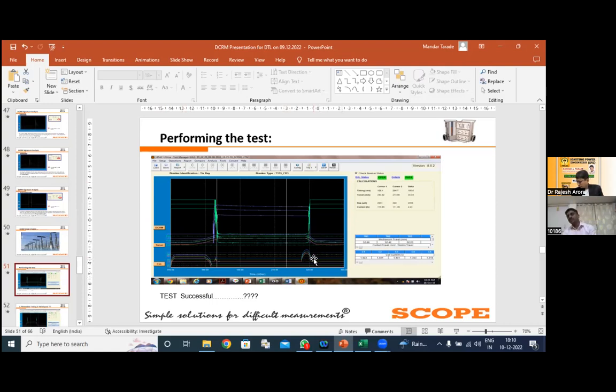One more distinction I want to give you: many people, at the time of performing the test or during preparing the setup, may think that delay TCO is the delay between close to open. It's not like that. Delay TCO is always the time from where your close command is initiated, from the 0th instant, to where you are issuing the trip command. That is the delay TCO.